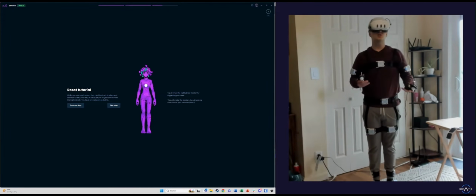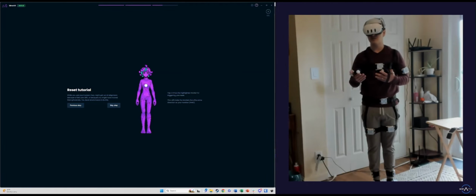So the biggest issue with IMU trackers is they tend to drift a little bit over time, which means that if there's even a slight amount off, that becomes additive every single time it goes through this loop of sending data, because it doesn't have any ground truth to anchor on. So if it's just slightly off, in a minute you won't notice it, in 10 minutes you might notice it, 30 minutes you probably will, an hour you definitely will. The better the IMU, the longer this drift time becomes. So we use the top-of-the-line consumer IMU available, the BNO.